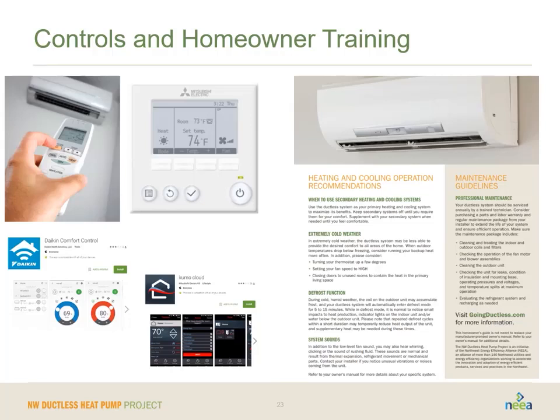Some of the maintenance items associated are cleaning the filter on the indoor head and checking the condensate line at least annually to make sure there's no blockages. The Northwest Ductless Heat Pump Project does provide a lot of collateral, and we'll show you in the resources at the end the website, where you can download these. They can be really nice pieces for you to use when you have the conversation with the homeowner, but you can also use collateral that has been developed directly from the manufacturer you're working with.